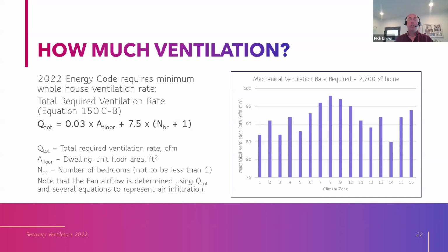Yeah, for high occupancy spaces, and I assume, Hank, you're talking about non-residential buildings more than single-family homes, because single-family homes are using this formula, number of bedrooms and conditioned floor area. That should scale pretty well. But non-residential buildings have ASHRAE 62.1, which has more of a formula using the expected number of occupants, like 15 CFM per person. Good question.